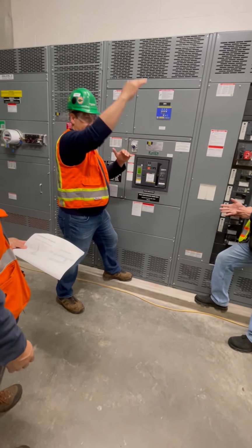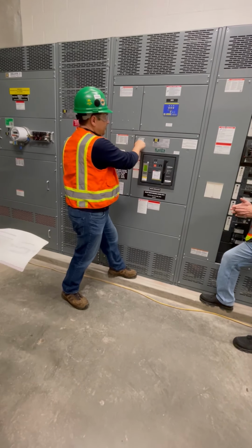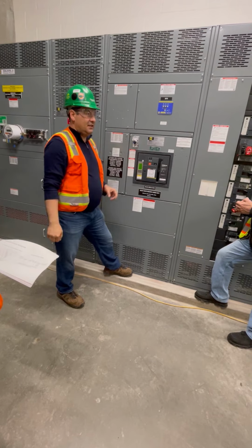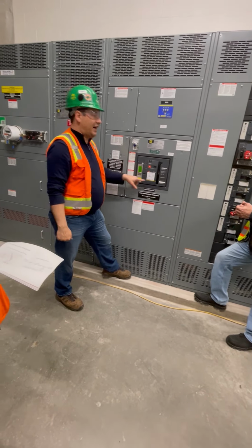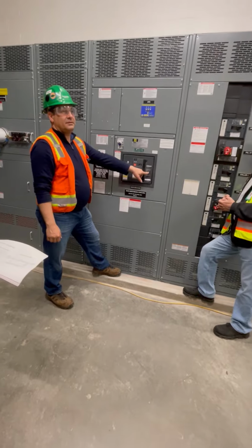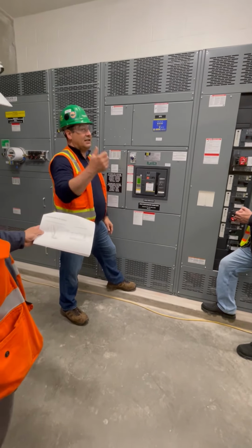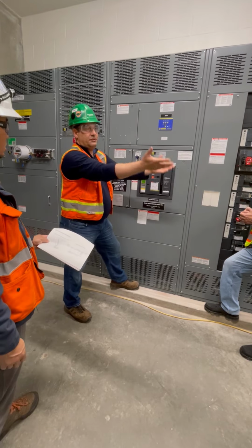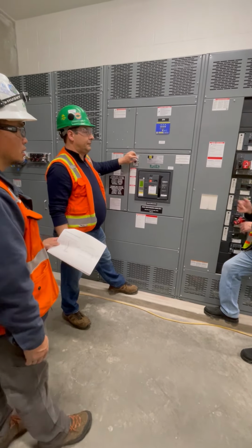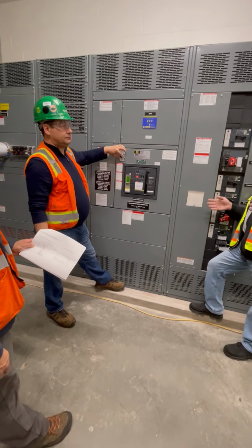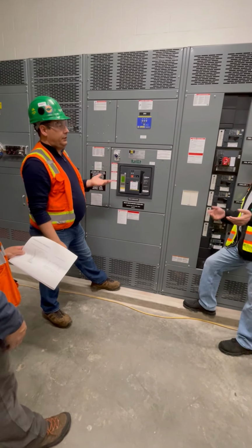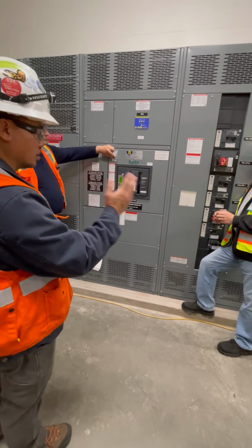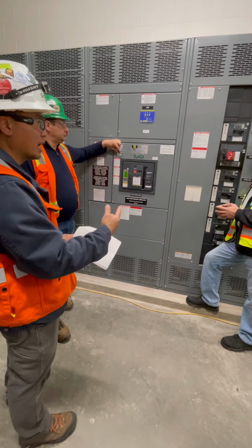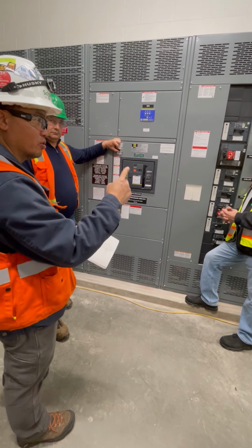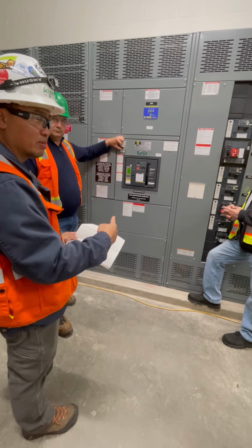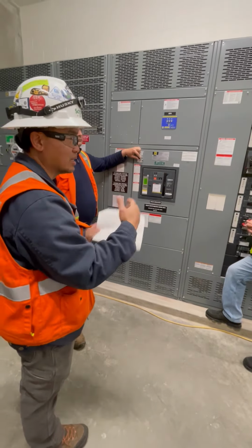Which matters when you have high arc flashes downstream. You put this in the on position, and it reduces the instantaneous to its lowest level. I think it's either 2 or 2.5 times 3,000, so it's 6,000 amps. So the breaker trips at 6,000, not at 30,000 on instantaneous. Therefore, it's reducing your magnitude downstream, and the arc flash won't be as big. It trips sooner, yes. The arc flash incident energy is a function of time and available fault current. So if you reduce the available fault current and the time, the incident energy will go down. That's the intent of the ERMS.